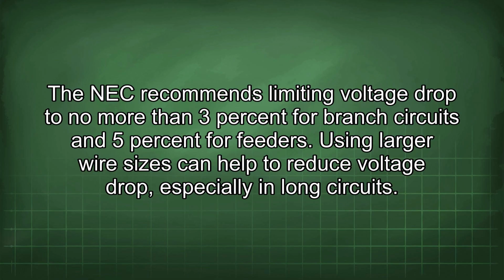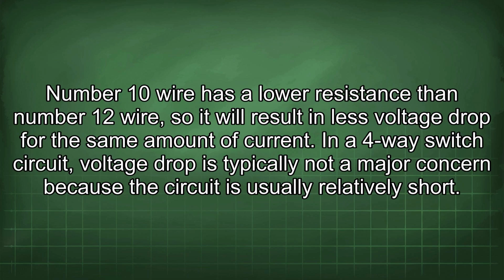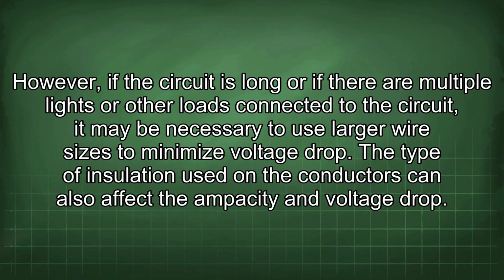Using larger wire sizes can help to reduce voltage drop, especially in long circuits. Number 10 wire has a lower resistance than number 12 wire, so it will result in less voltage drop for the same amount of current. In a four-way switch circuit, voltage drop is typically not a major concern because the circuit is usually relatively short. However, if the circuit is long or if there are multiple lights or other loads connected to the circuit, it may be necessary to use larger wire sizes to minimize voltage drop.